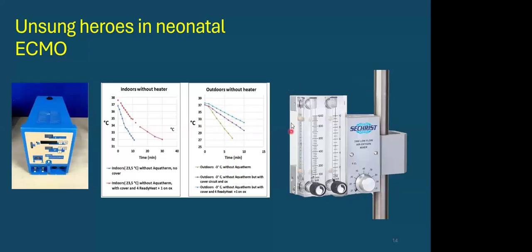If we look at the picture on the right, this is what I was referring to with the blenders, gas blenders. Most hospitals only have adult blenders, and the blenders they have are not pediatric or neonatal focused and will not be ideal for the ECMO circuits. Unfortunately, it's often just temporary until we can get them back to our facilities. But if you look at the high flow, it goes in gradations of a liter up to about 10 liters. If you're looking at running gas flows of 200 or 300 or 400 mL, as you often may have to do in neonatal patients, it's very easy to see how you can make those mistakes using a high flow blender.